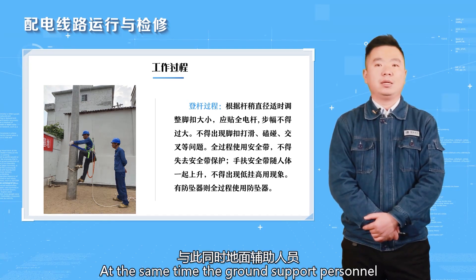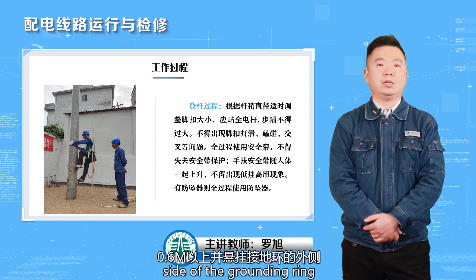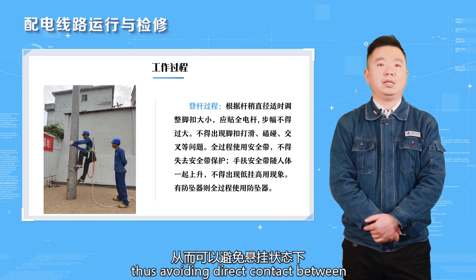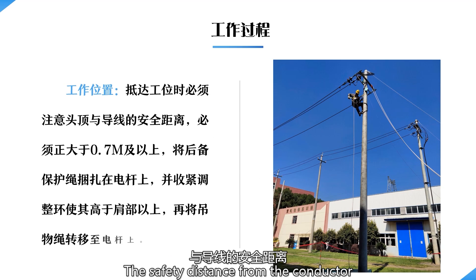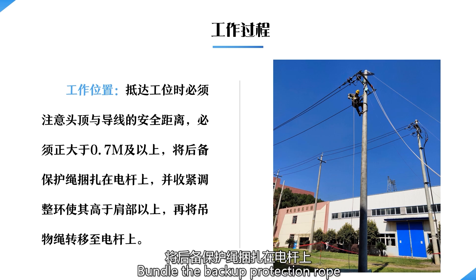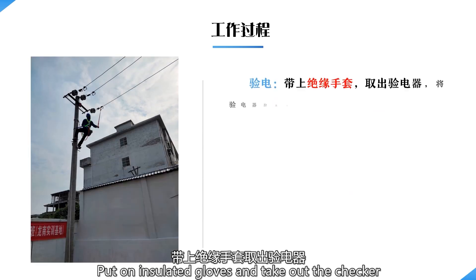At the same time, ground support personnel drive the grounding stake into the ground 0.6 meter or more and hang it on the outer side of the grounding ring — that is, the position other than the back of the operator on the pole — thus avoiding direct contact between the grounding wire and the operator. When arriving at the workstation, the safety distance from the conductor must be greater than 0.7 meter. Bundle the backup protection rope on the electric pole, tighten the adjusting ring so that it is above shoulder level, then transfer the rope to the pole. Put on insulated gloves and take out the checker.